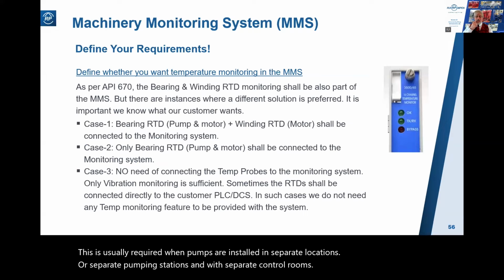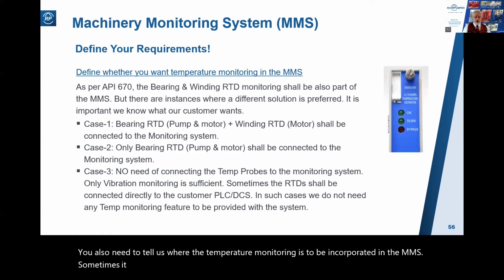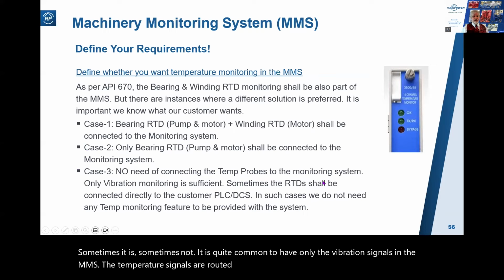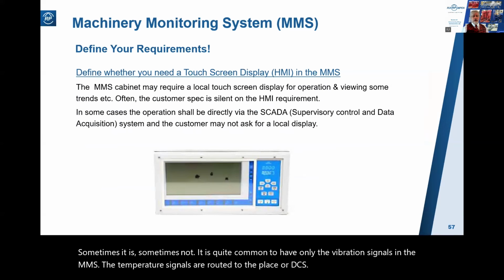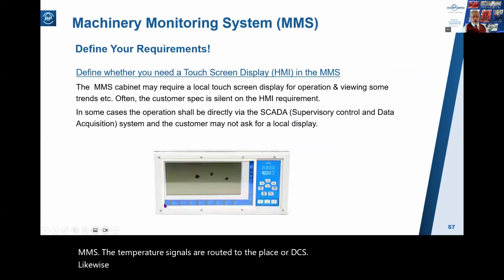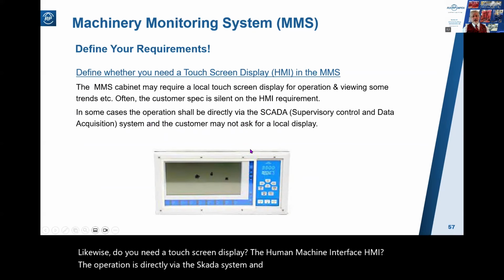You also need to tell us whether temperature monitoring is to be incorporated in the MMS. Sometimes it is, sometimes not. It's quite common to have only the vibration signals in the MMS. The temperature signals are routed to the PLC or DCS. Likewise, do you need a touchscreen display? The human machine interface, HMI. Frequently, the operation is directly via the SCADA system, and the customer doesn't need a local display. But sometimes they do. It's expensive kit.